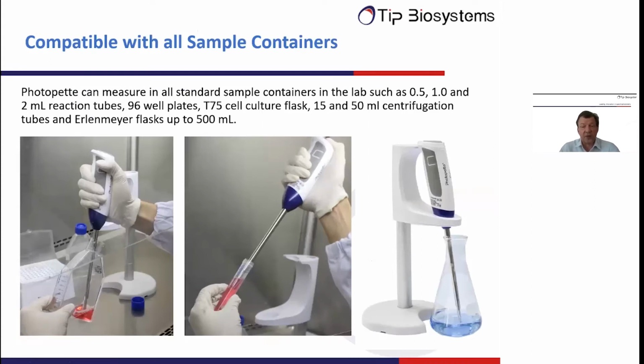We have designed the Photopette in a way that is compatible with most sample containers that you find in the lab. Here on the left, you see direct measurements of mammalian cell density in what's called a T75 cell culture flask. In the center here, you see a measurement in a typical centrifugation tube of 15 or 50 milliliter, and on the right, measurements in an Erlenmeyer flask. The instrument can also be used in reaction tubes of 500 microliter to 2 milliliter, and can also be used to measure 96 well plates.